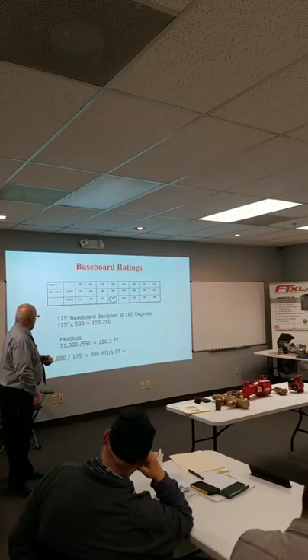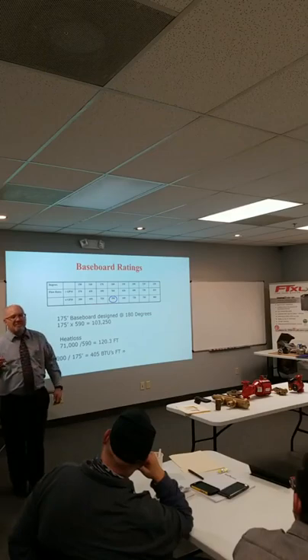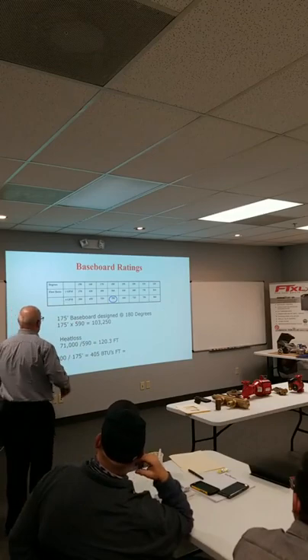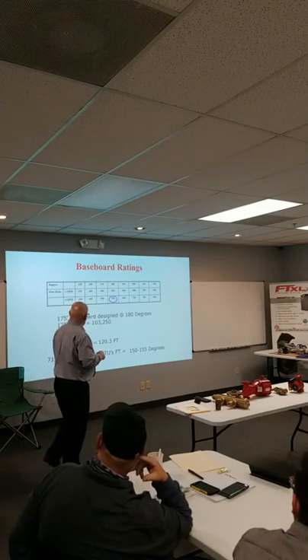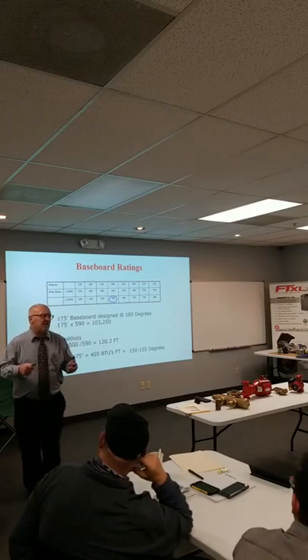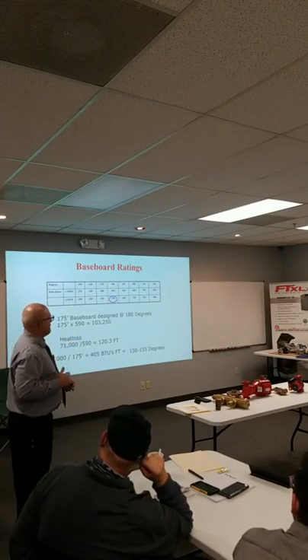So now we do that calculation. Now we say 71,000 BTUs, we have 175 feet of baseboard. All I need is 405 BTUs per lineal foot now to satisfy the heat loss. Okay, what water temperature do I need now? At design, if we designed this around zero and that's our heat loss, my maximum water temperature will be 150 to 155. Not 180, which is what we're running right now, whether it's 60 outside or zero outside.